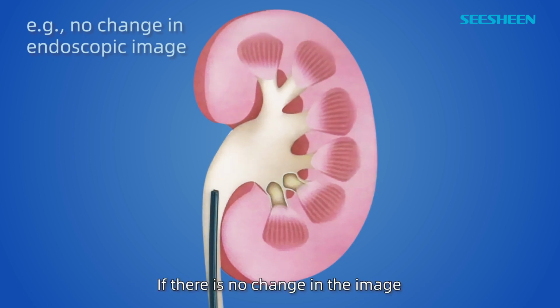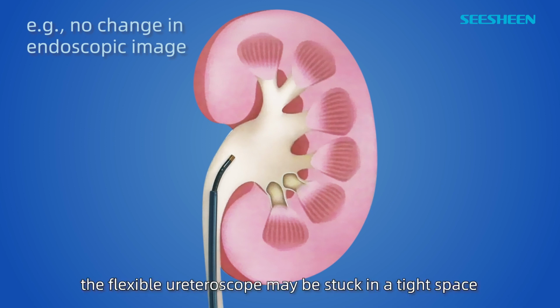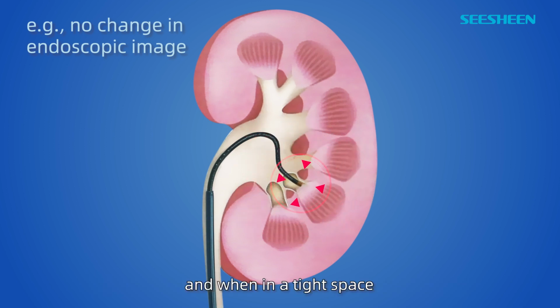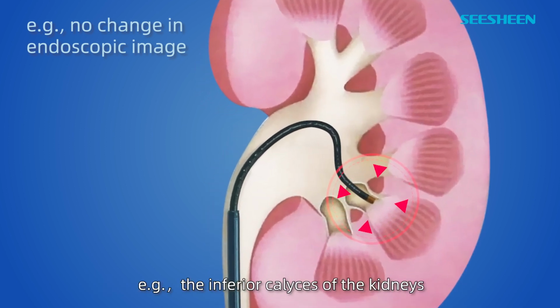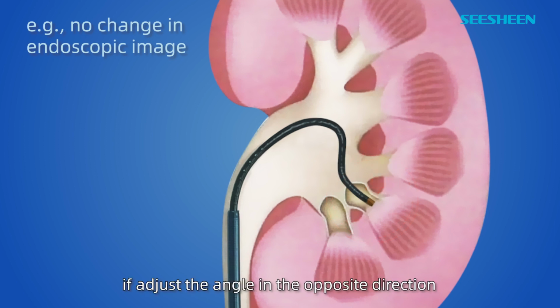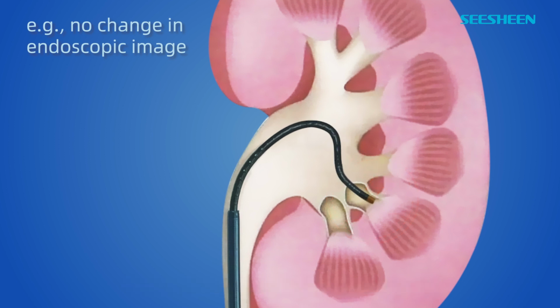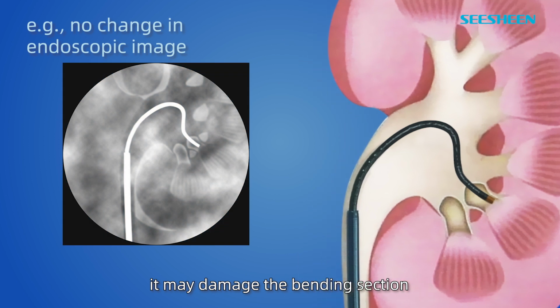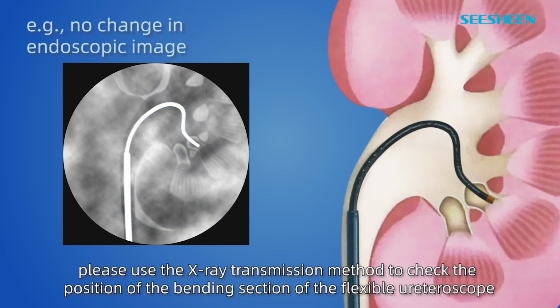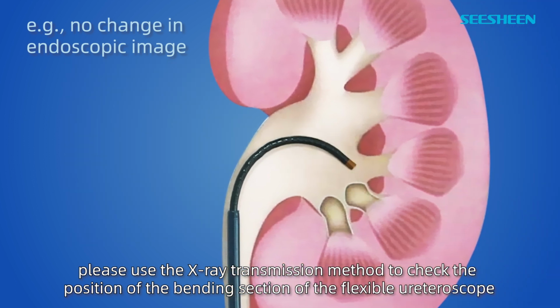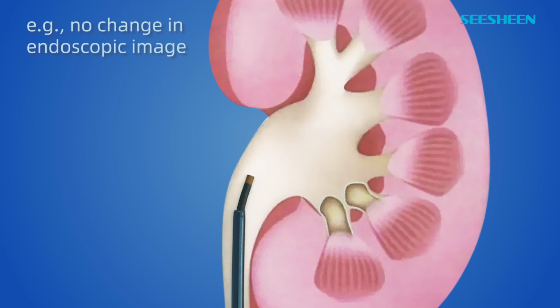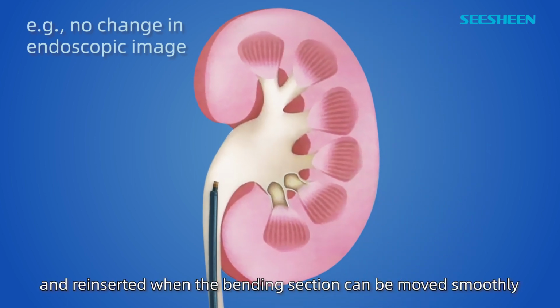If there is no change in the image, even if you adjust the angle of the bending section, the flexible ureteroscope may be stuck in a tight space. When in a tight space, e.g., the inferior calyces of the kidneys, if you adjust the angle in the opposite direction, it may damage the bending section. In this case, please use the X-ray transmission method to check the position of the bending section of the flexible ureteroscope, as well as its shape, then move the ureteroscope gently and reinsert it when the bending section can be moved smoothly.